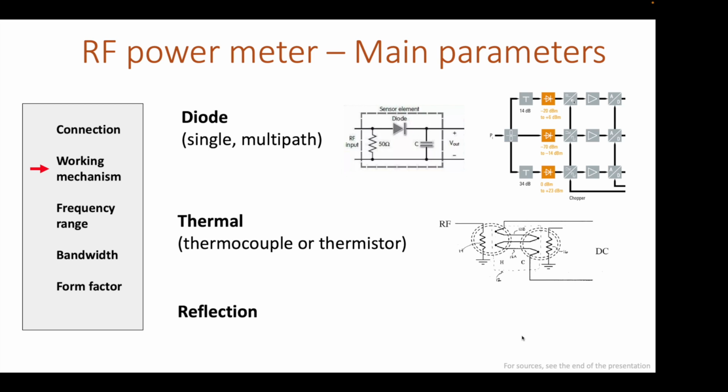And then finally there is the reflection model as well, that usually works with the directional coupled port. That is another mechanism in itself, and there of course you don't consume the power of the transmitter, but you basically tap into it via another line.